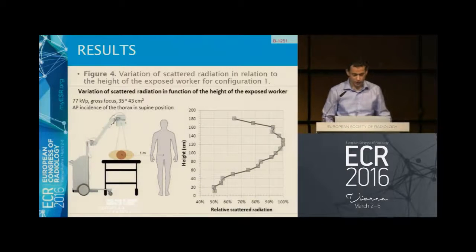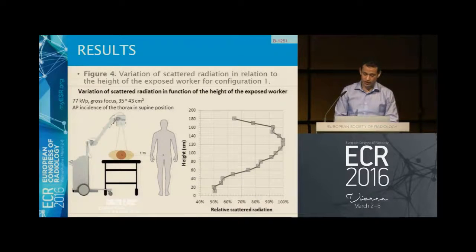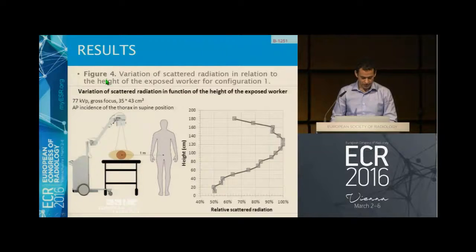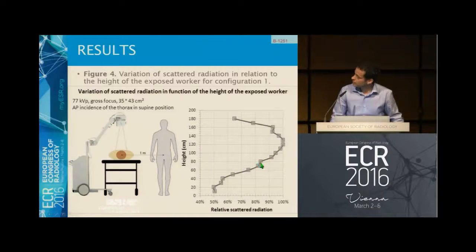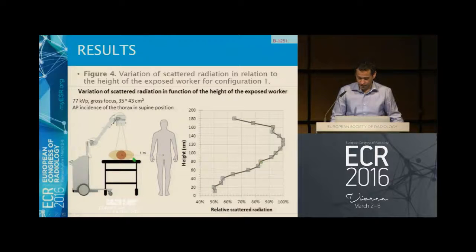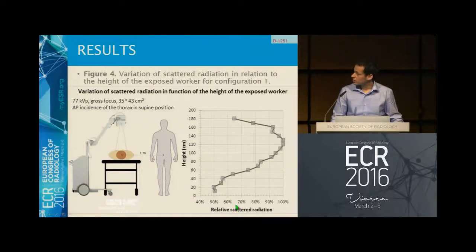In figure four, we also show the variation of scattered radiation in relation to the height of the exposed worker for configuration one, with an example at a distance of one meter. As expected, beneath the table the dose decreases very much. This has to do with the bed that the patient is in, and also the bars and some metal structures found in some beds. Most of the scattered radiation goes upward in the direction of the head, the chest, and the eyes.